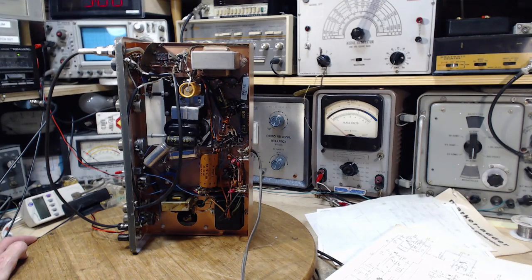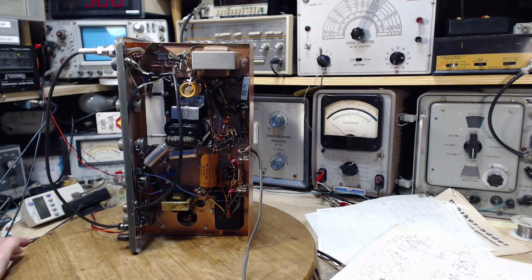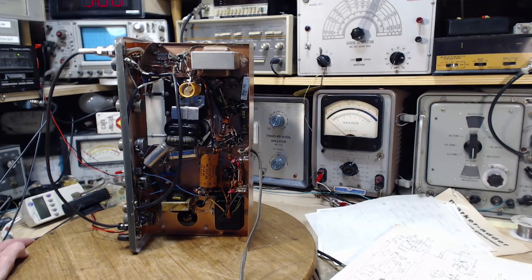They just installed it at a new building and hooked it up, and it was screaming at them. But it was screaming in a weird pattern. Kind of a come and go and up and down and this and that. And they'd heard something about stray current from the Toronto Transit System. That's a DC operated streetcar subway system. Yeah, an extensive streetcar subway system. And they wanted to know if we knew anything about it. And so it came to me.